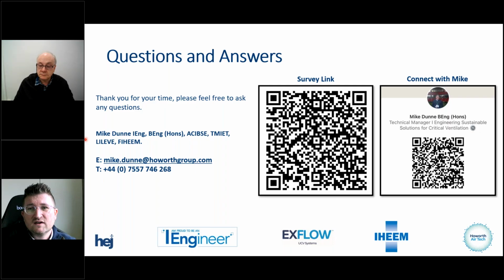was saved. Like I said in the presentation, sustainability and reducing consumption in healthcare is the biggest challenge, particularly when it comes to HVAC systems, which is the most energy hungry piece of kit as engineers we're probably going to deal with. So if we can reduce the load by switching it off in the evening, along with the UCV and the AHU together through that electrical interlock that I showed you, and then we monitor the out of hours to make sure that it doesn't drop below 18 degrees.